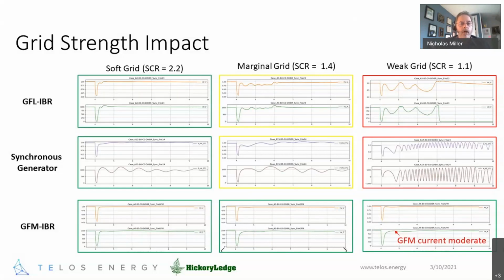The yellow ones, two cases in the middle, are stable in the sense that they actually make it, but they violate NERC and WECC voltage swing limits. So those are fails from a system performance point of view, but it's illustrative: if the system gets through a wiggle, it's somewhere not acceptable, but neither is it a complete fail. On the right, the two red boxes are actual fails where the generation trips because it didn't survive.